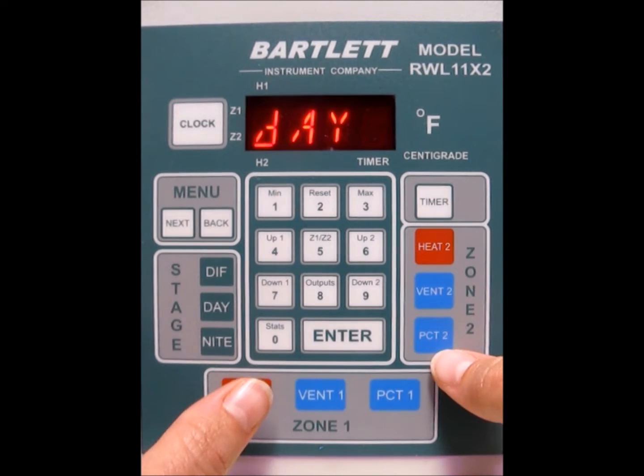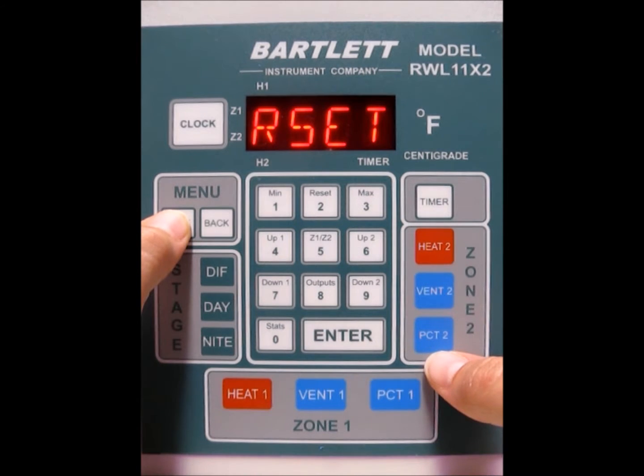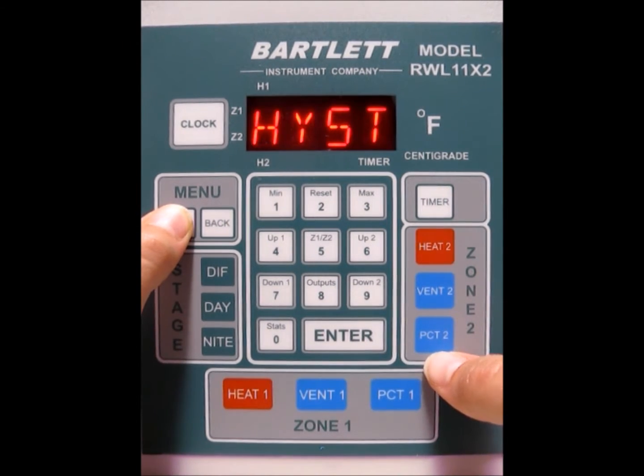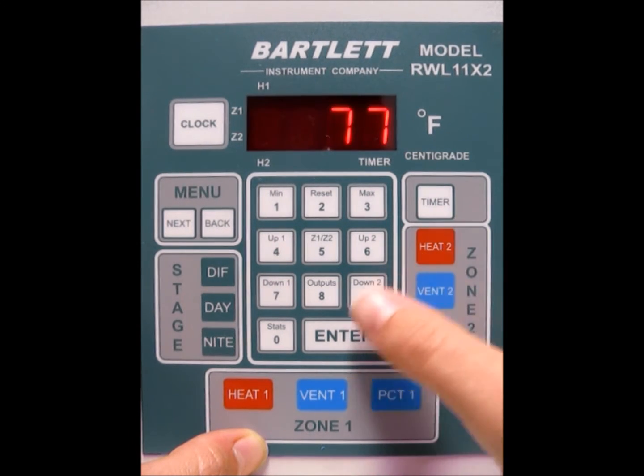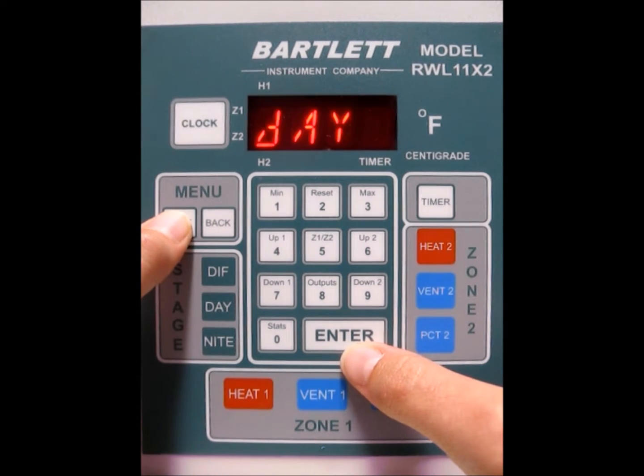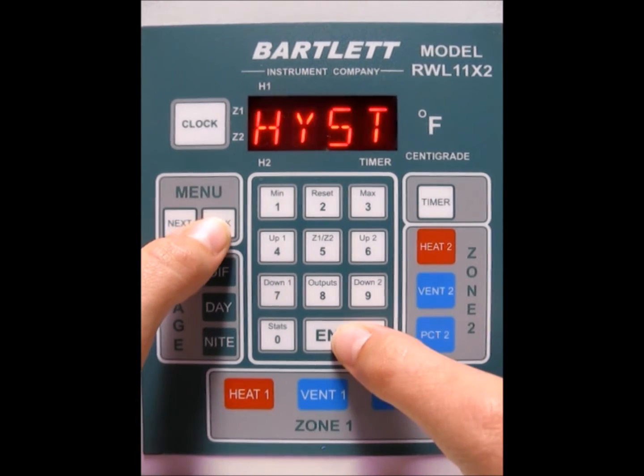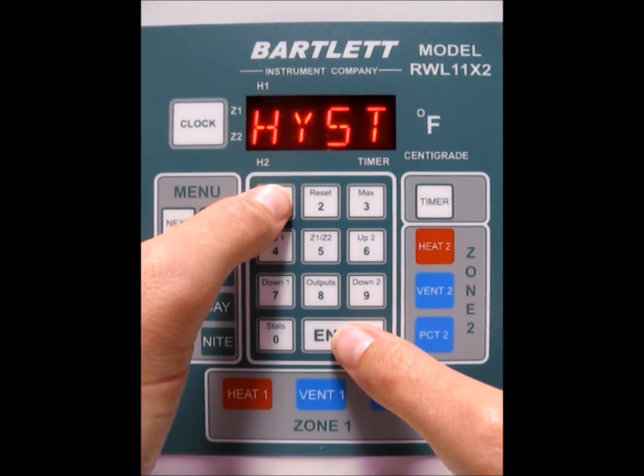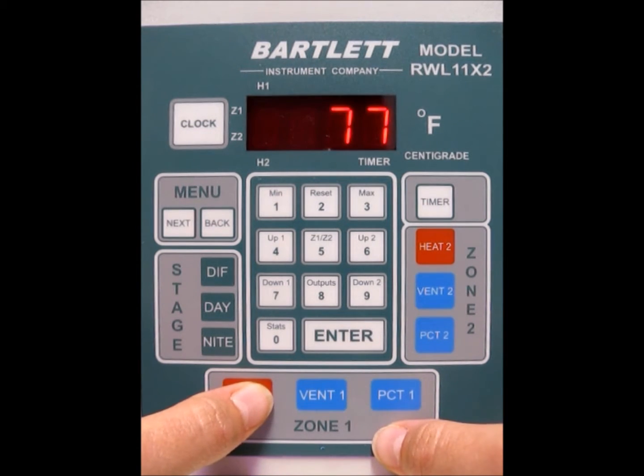Now we want to check the hysteresis because we're going to program the heat 1 and 2 outputs. Press the next button until HYST comes on the screen, then press enter. You have the option for a hysteresis of 1, 2, or 3. This allows for a separation above and below the output temperature for more efficient cycling of appliances. We'll go ahead and press the 1 button, then press enter.